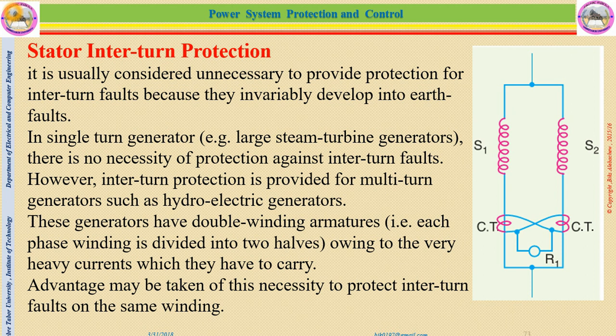Stator interturn protection. It is usually considered unnecessary to provide protection for interturn faults because they invariably develop into earth-faults. So, stator interturn protection is required only for double or more than double winding. For a single turn generator, for example a large steam turbine generator, there is no necessity to protect against interturn faults. However, interturn protection is provided for multi-turn generators like hydroelectric generators. Those generators have double winding armatures. For example, each phase winding is divided into two halves owing to the very heavy currents which they have to carry. So advantage may be taken of this necessity to protect against interturn faults on the same winding.